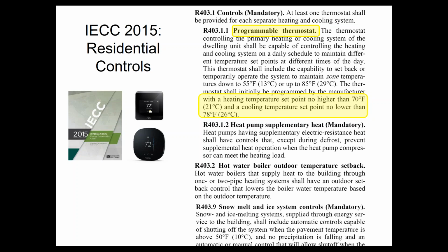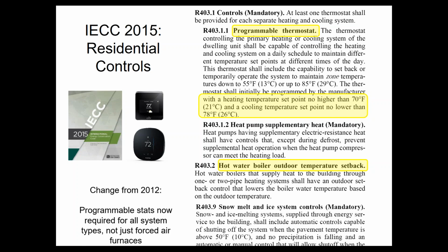There are some requirements for heat pumps to make sure that you're using the compressor heat pump instead of your electric resistance heat when the compressor is able to handle the load, right? And that's nothing new either. Boilers have to have outdoor temperature setback. That shouldn't be anything new either, because the DOE rules since 2012 require that anyway. Every residential boiler in the entire country, irrespective of state codes, has to have some type of automatic means of water temperature adjustment, which generally means outdoor air reset. And you have to have controls for snow melt systems, so they're only running when it's cold outside and you have precipitation.